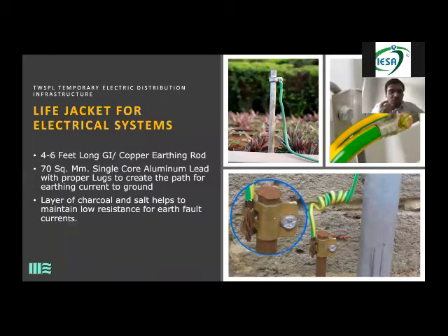So again, I'm reading the question. If you're doing an event in any hotel, which earth is possible to use? I got the question. So basically, in a hotel, if you're using the house power from the hotel, the only earthing you require is the body earth. Whenever you're taking power from BSES, Tata, hotel, anywhere, the neutral is always earthed from their system, because that is the most important thing. The only earthing you need to do in a hotel is the body earth.